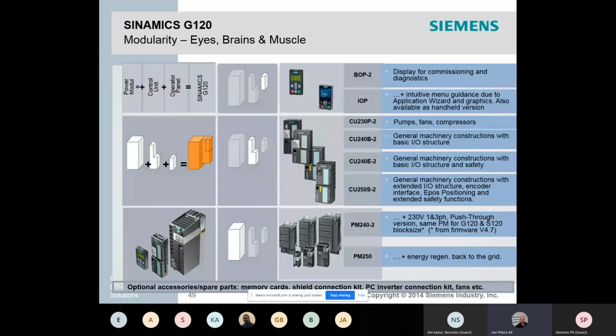There is a PM240-2, which comes in 230 volt single and 3-phase, and then 3-phase 480 volt. The same power module here is shown for both the G120 and the S120 versions. There is a PM250, which has regenerative capabilities back to the grid as well.